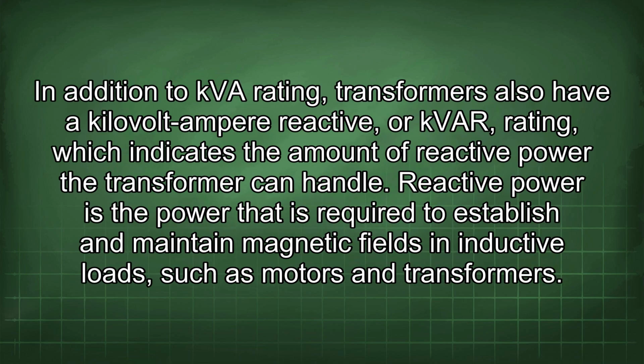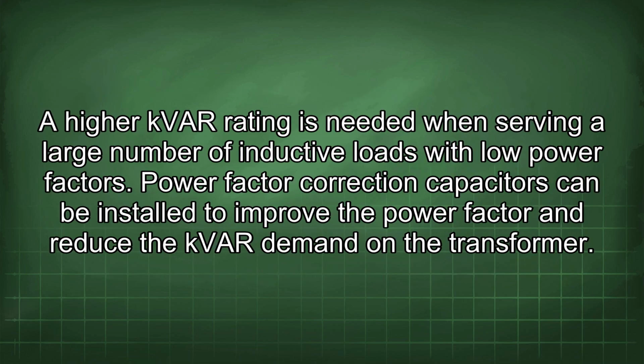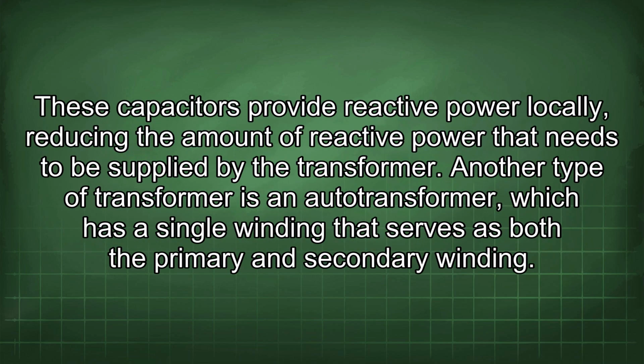In addition to kVA rating, transformers also have a kilovolt ampere reactive, or kVAR, rating, which indicates the amount of reactive power the transformer can handle. Reactive power is the power that is required to establish and maintain magnetic fields in inductive loads, such as motors and transformers. A higher kVAR rating is needed when serving a large number of inductive loads with low power factors. Power factor correction capacitors can be installed to improve the power factor and reduce the kVAR demand on the transformer. These capacitors provide reactive power locally, reducing the amount of reactive power that needs to be supplied by the transformer.